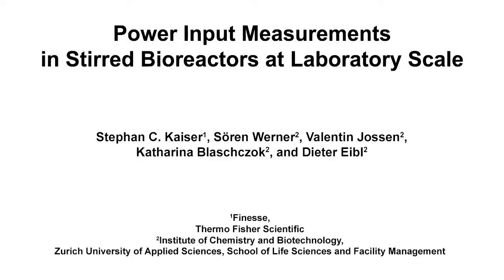The overall goal of this protocol is to determine the power input in stirred laboratory bioreactors based on torque measurements. The main advantage of this technique is that commercially available sensors can be used for benchtop scale investigations, which enables the user to perform measurements for scaling up studies. Visual demonstration of this technique is critical because the proper installation of the torque transducer is important for reliable measurements.